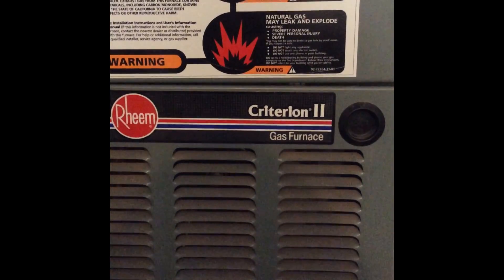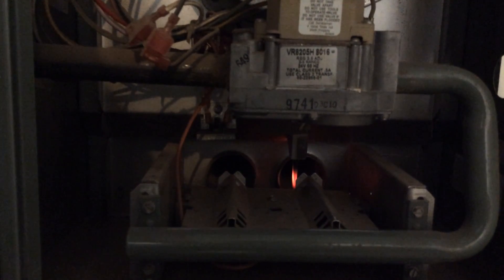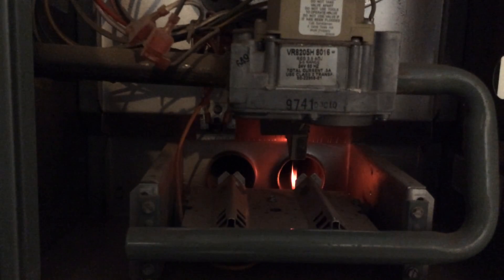Welcome to how to fix your Rheem Criterion II gas furnace with 2 burners. The lighting process takes about a minute, and the hot surface igniter comes on at 50 seconds. You can see it glowing.